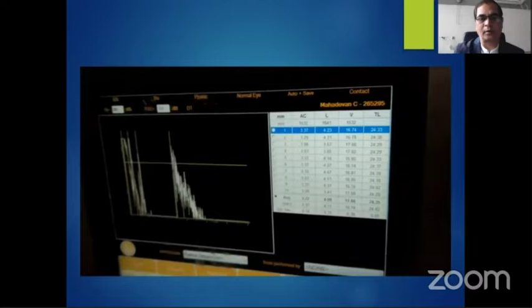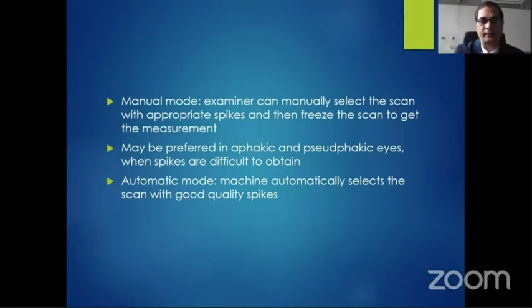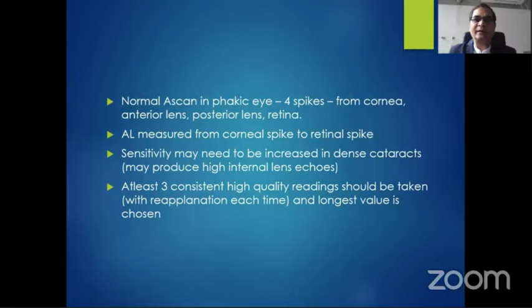In automatic mode, it takes 10 to 15 readings, and then it gives the best one. In manual mode, the examiner can manually select the scan with the appropriate spike and then freeze the scan to get the measurement. It may be preferred in aphakic and pseudophakic eyes when the spikes are difficult to obtain. While in automatic mode, the machine automatically selects the scan of good quality, like we have seen in this video. A normal scan has 4 spikes: first from the cornea, then anterior lens capsule, posterior lens capsule, and retina. The axial length is from the corneal spike to the retinal spike. The sensitivity may need to be increased in dense cataract. At least 3 consistent high quality readings should be taken.